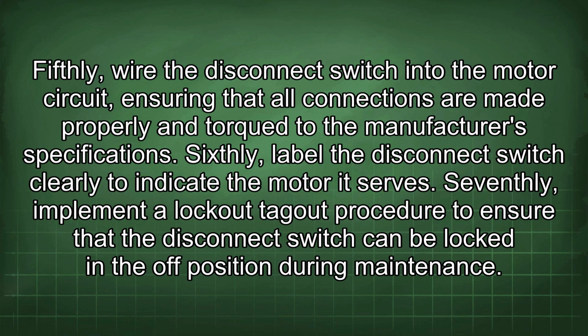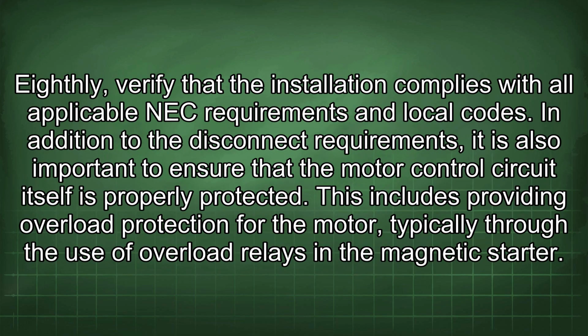manufacturer's specifications. Sixthly, label the disconnect switch clearly to indicate the motor it serves. Seventhly, implement a lockout-tagout procedure to ensure that the disconnect switch can be locked in the off position during maintenance. Eighthly, verify that the installation complies with all applicable NEC requirements and local codes.